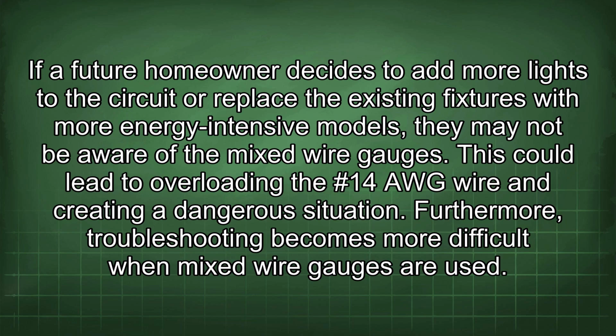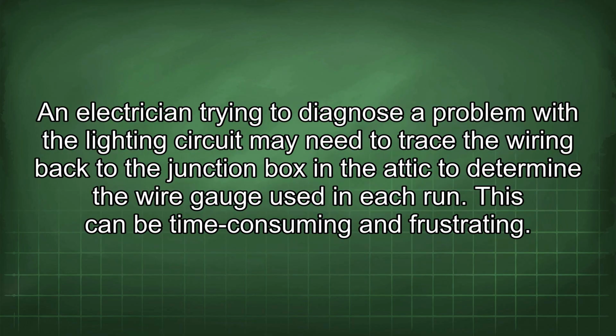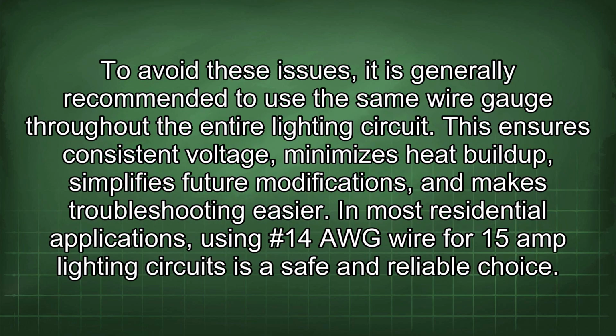Furthermore, troubleshooting becomes more difficult when mixed wire gauges are used. An electrician trying to diagnose a problem with the lighting circuit may need to trace the wiring back to the junction box in the attic to determine the wire gauge used in each run. This can be time-consuming and frustrating. To avoid these issues, it is generally recommended to use the same wire gauge throughout the entire lighting circuit. This ensures consistent voltage, minimizes heat buildup, simplifies future modifications, and makes troubleshooting easier.